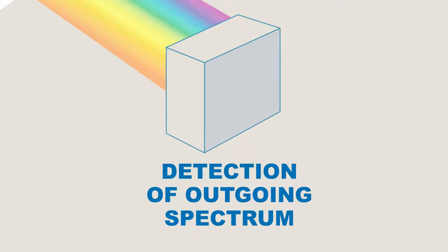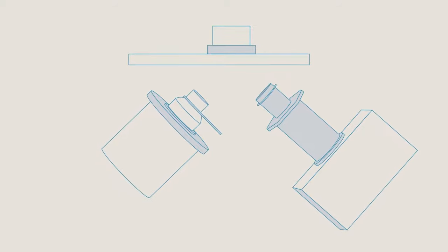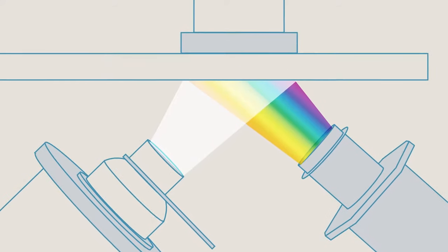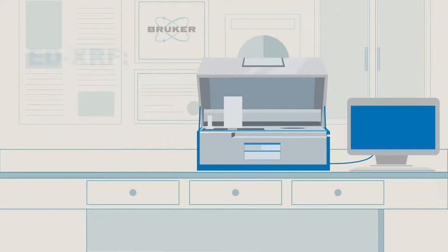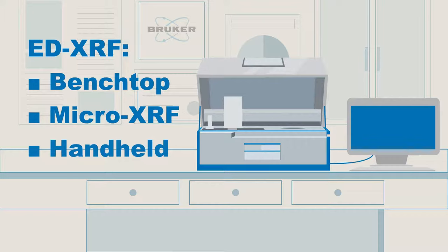The more channels, the better the resolution. Because all radiation from the sample is collected directly after the sample, the power of these systems can be lower. This makes EDXRF perfect for benchtop systems and low-intensity setups like micro-XRF or handheld XRF.